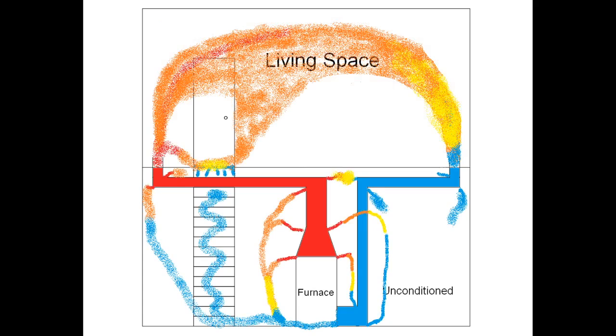In reality, what happens in most buildings, especially residential buildings, is that we have leaking ductwork. And the hot air enters the trunk above the furnace through the plenum and then leaks into the basement, whereupon it gives up its heat to uninsulated masonry walls and concrete floor, and gets sucked into the returns through leakage to be heated again and circulated again in the basement. That's all waste because it hasn't gotten to the living space, and it's not really warming up the basement because of the uninsulated walls.